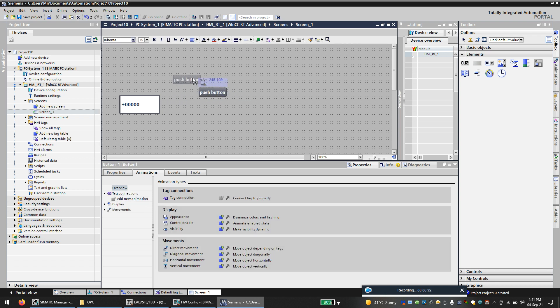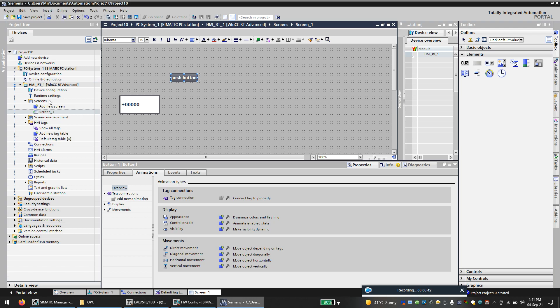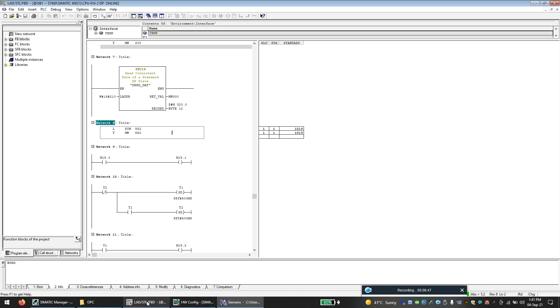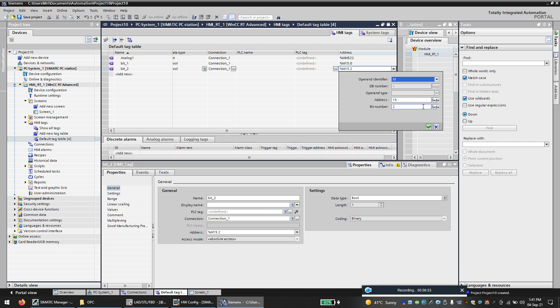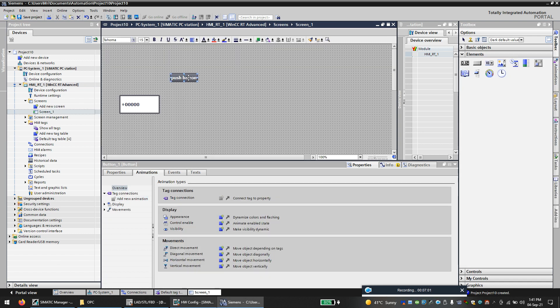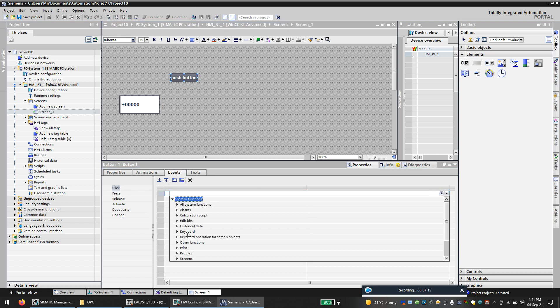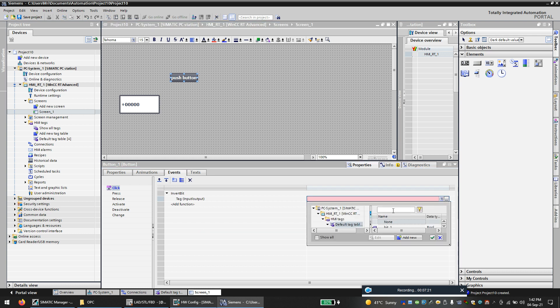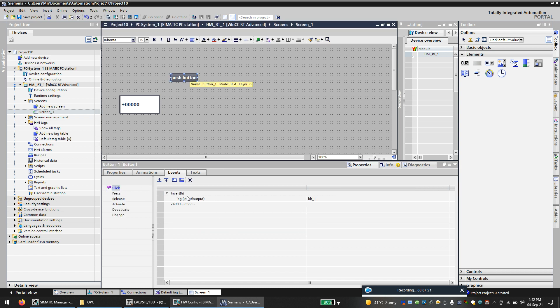Now I will configure a push button. So when I click on this, I need to activate the bit M15.0. This should be M15.1. So when I click on this, that is when I click, you have a lot of functions here. So I will set bit, I will use this function maybe. I will activate bit number one. So when I click, I will activate bit number one.